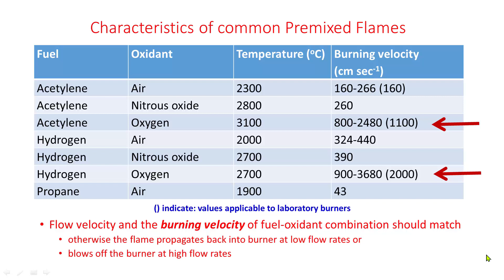This table shows characteristics of common pre-mixed flames. This column tells about the temperatures and this column about the burning velocity. Acetylene oxygen has a burning velocity very high. Same is the case with the hydrogen oxygen flame. Flow velocity and the burning velocity of the fuel oxidant combination should match, otherwise the flame propagates back into the burner at low flow rates or blows off the burner at high flow rates.